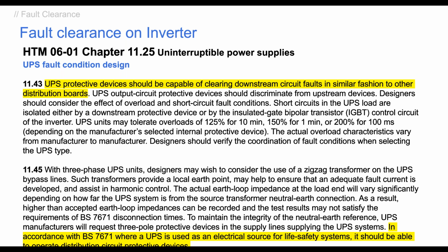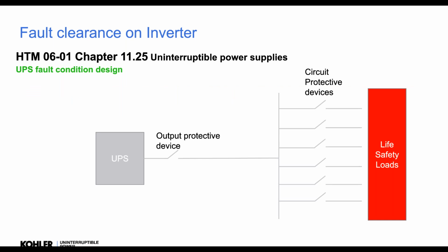HTM effectively follows that. It gives you the reason why. UPSs have got a very limited short circuit, but basically it says you have to comply with 7671 and be able to operate the downstream protective devices with it. There's some things in there that are a little confusing. Any questions on that, you can speak to us, but mostly it's correct and says you have to operate the downstream devices. Basically, because if you have a fault here, you want to open this device to keep everything running.